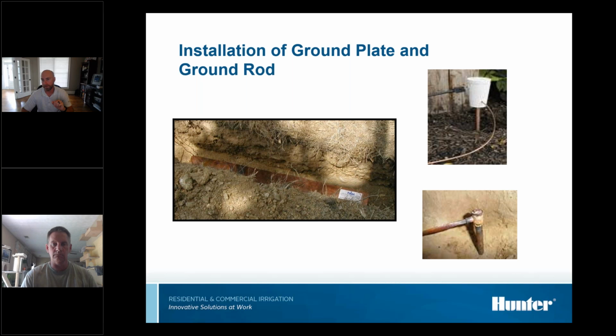The one on the right is called a CAD weld. It's basically got almost like explosive gunpowder in it. You light the charge off and it almost welds the ground plate to the ground lead together. Don't do that before you get on an airplane, because they're going to do that to your hands and you're probably going to get thrown in jail. Just FYI there. Typically we don't see ground rods much anymore, still kind of common, but a lot of guys are moving to the ground plate.